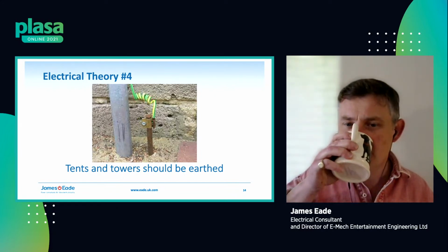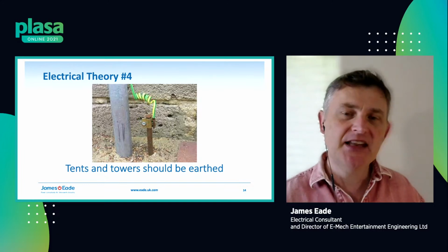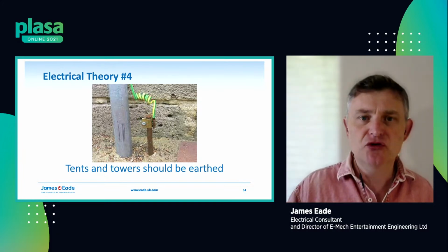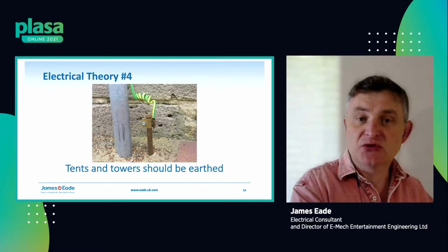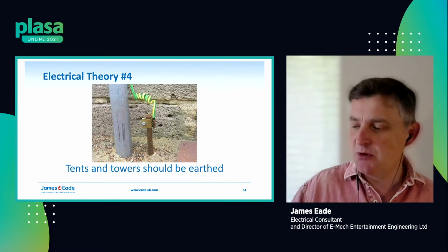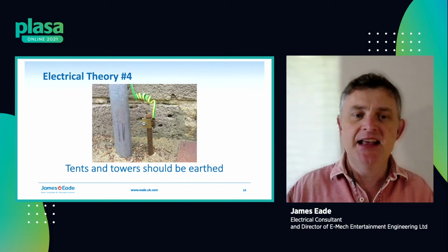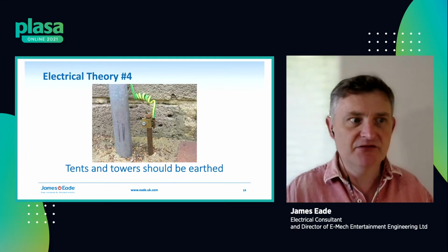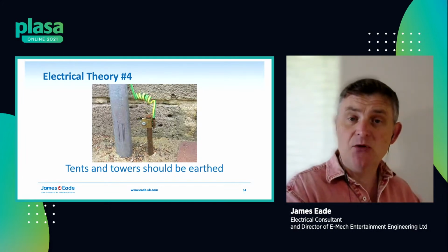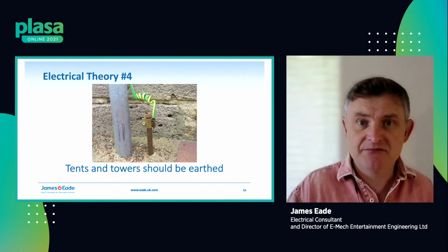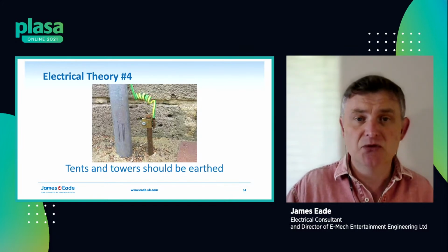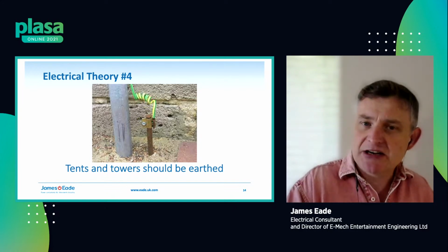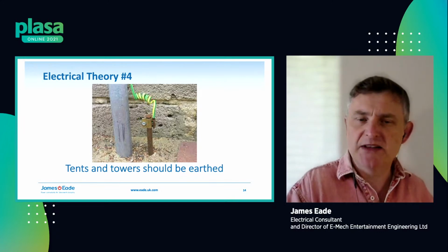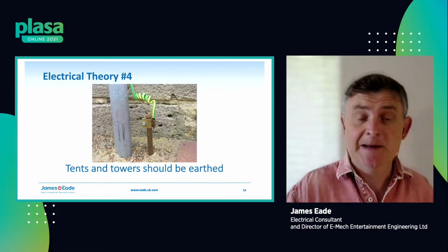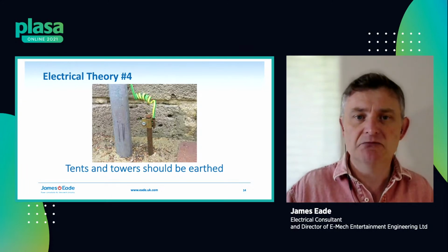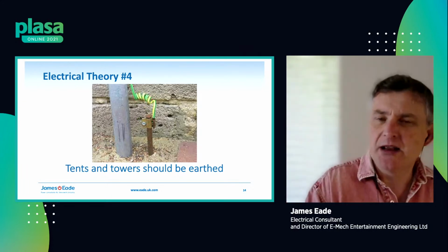Tents and towers should be earthed. Again, this is a common theme I find on training courses. We talk about electrical safety, protective bonding, and people often say, well, we put an earth rod down at the front of a tower. And when asked why, they say, well, for electrical safety. Is it for lightning protection, or is it protective bonding to limit the voltage differences in the tower if a fault occurs? When you start scratching beneath the surface a little bit, no one is really sure why this happens. I know some tent companies do it religiously, put earth electrodes down and connect them to their structures. But why? Why would we want to do that?